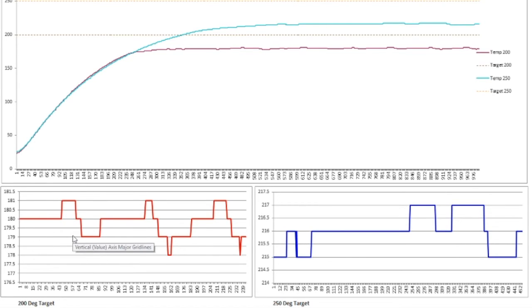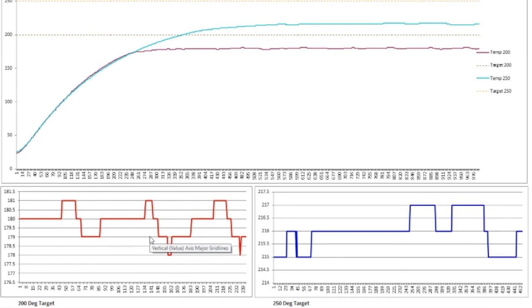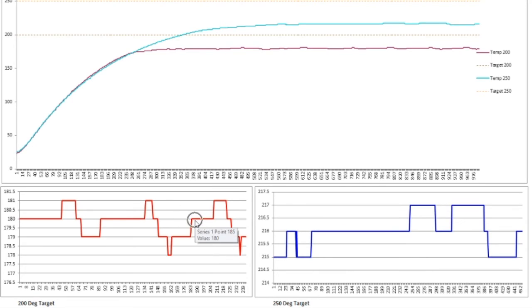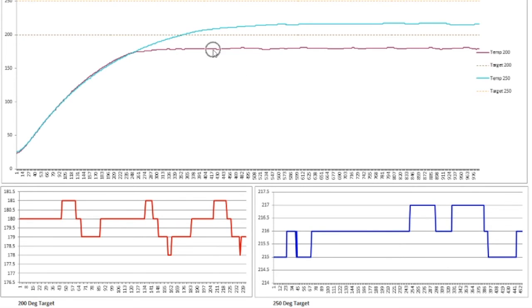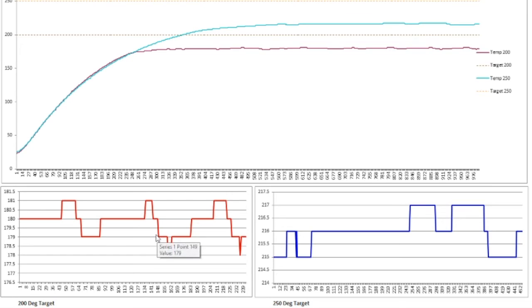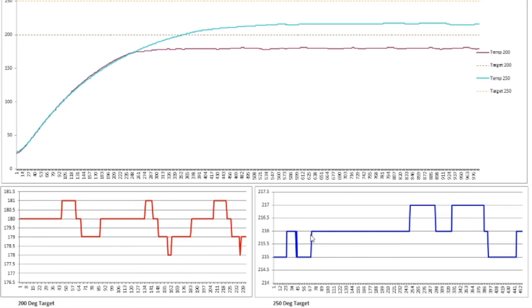But you can see here, the 200 is really a good example of what you'll have in a dead time type calculation where we spike up. And because if you notice the average is about 180. So we overrun to about 181 and we typically fall down to about 179. We jump up to 181, fall to 179. In certain cases, we even fall lower to 178. Here we had two polling cycles at 178 before we jumped back up to 179 and then climb back up to our average. So this pattern basically repeats itself. And again, you can kind of see it in the pattern up here versus here. That's what these bumps are. I've just changed the X domain to make it more prominent here. So you can kind of see it. So this has been really interesting for me because again, I didn't expect the bigger deltas but I did get the same stuff from PID.